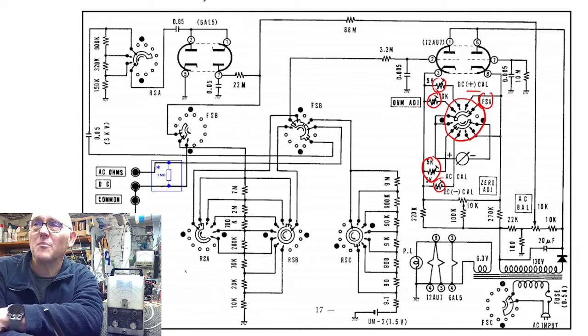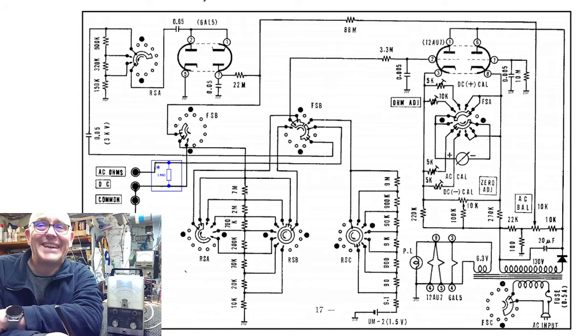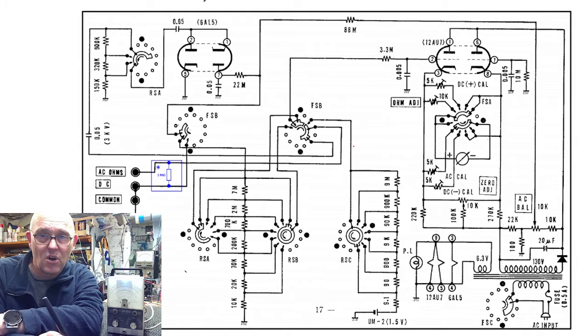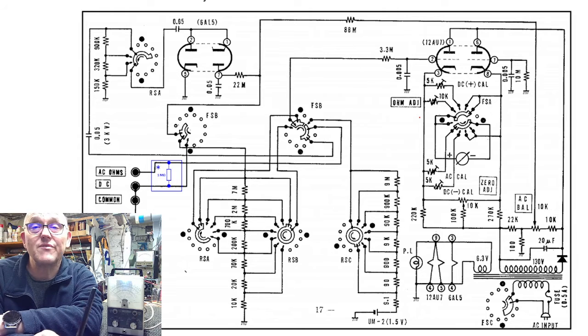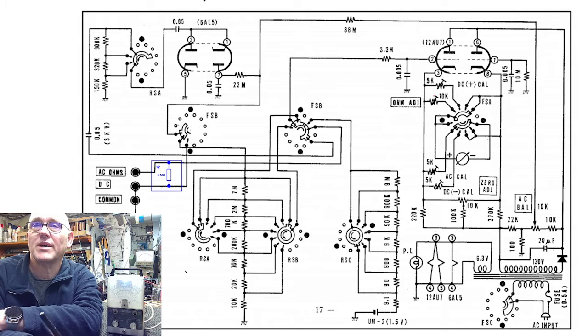So if you're going to calibrate, let's say for DC voltage, the best thing to do is select a range. Let's say you select the 5 volt range and then put a 5 volt DC in there so that you can take the meter to the full scale deflection. It's very important to calibrate at full scale deflection because these meters are designed to be accurate at full scale and then have 3% deviation from full scale at the rest of the range. Okay, that's the one thing. What other things did I miss?